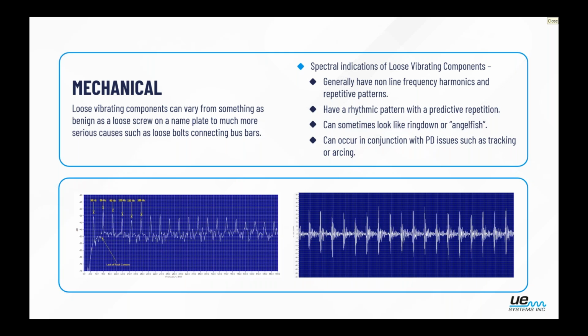And then when we actually look at it as the sample itself over time, this is a great indicator of something mechanically loose. So you see each one of these abrupt impacts, and I can tell that's an impact because it has almost this triangle arrowhead shape to it. So we're seeing the impact in the ring down of the event. So something is actually hitting another piece of equipment inside there. So very, very good example of mechanical impact.